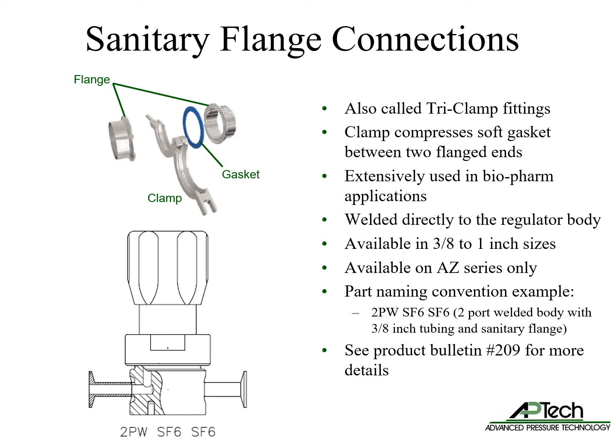Sanitary flanges are often called tri-clamp fittings. This connection clamps a soft gasket between two flanged ends to seal, and is used extensively in biopharm applications. The sanitary fitting is welded directly on the AZ body in 3/8 to 1 inch sizes. An example of a part configured with sanitary flanges is 2PW-SF6-SF6, meaning a two-port welded body with 3/8 inch tubing and sanitary flanges. For more information, see product bulletin number 209 at AP Tech's website.